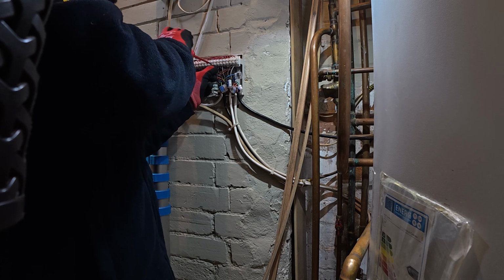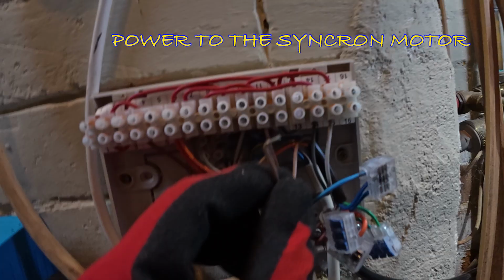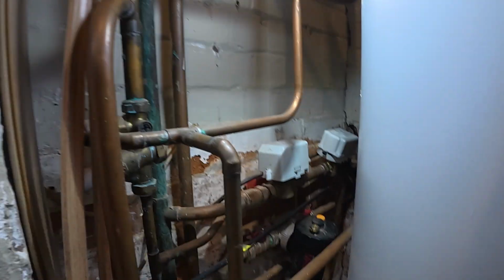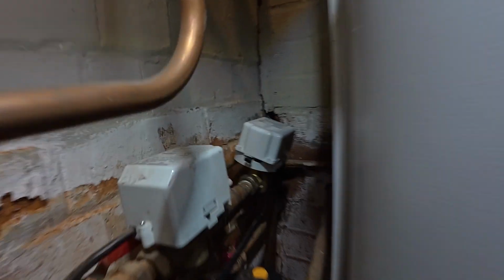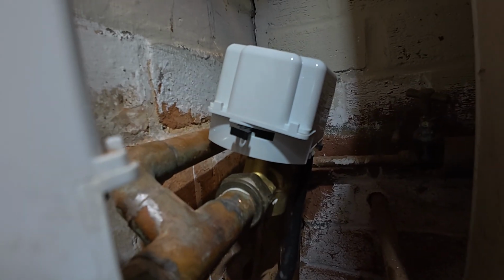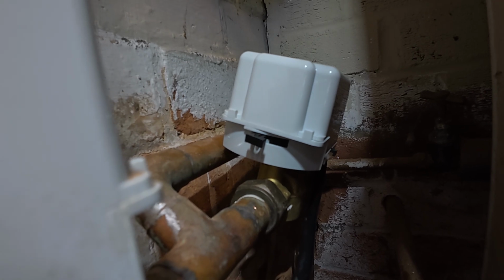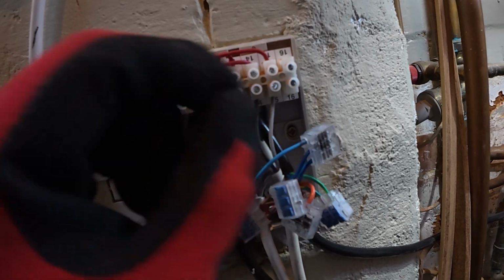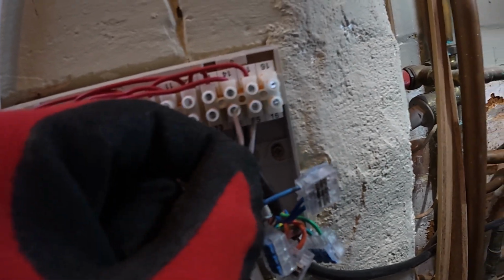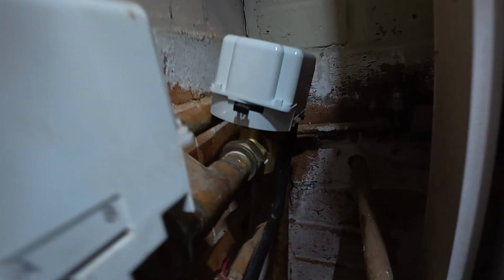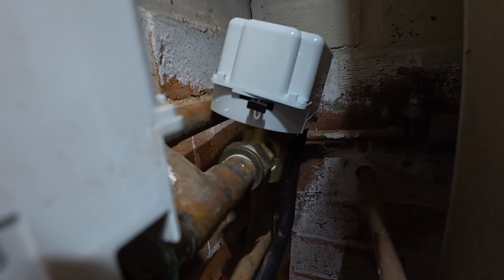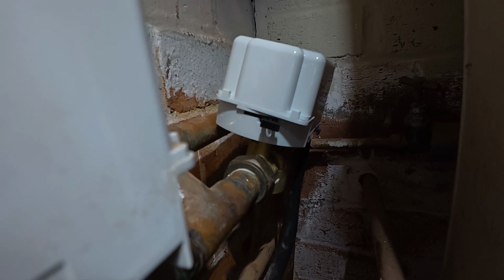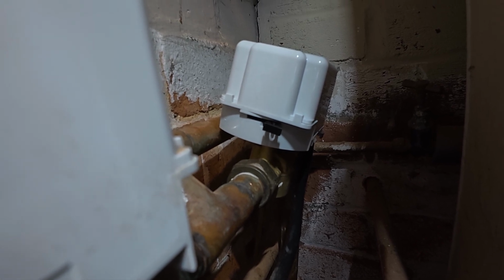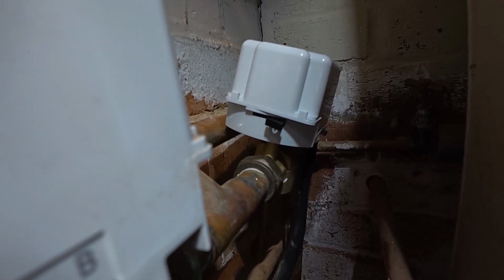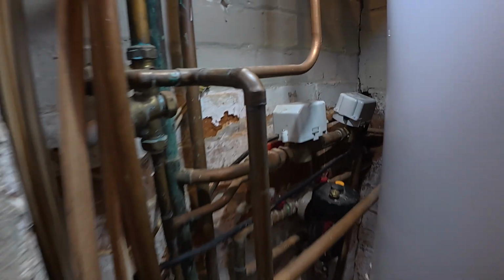just take out the brown, which is the power for the zone valve. So here is the cable for the motorized valve over there, back there. You can see the black lever where it is. To touch it and give it power, which is the one going to the cylinder stat. That motor's moved over. It's clicked, and you can probably hear the pumps kicked in. And now the hot water circuit is getting hot.